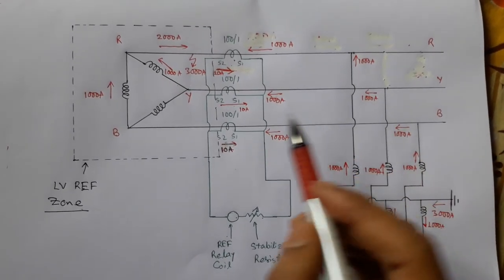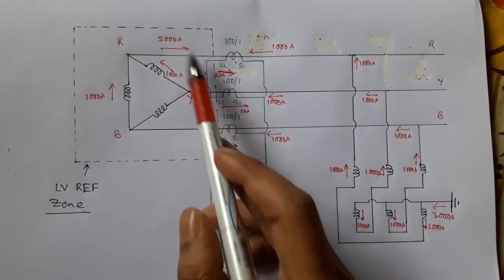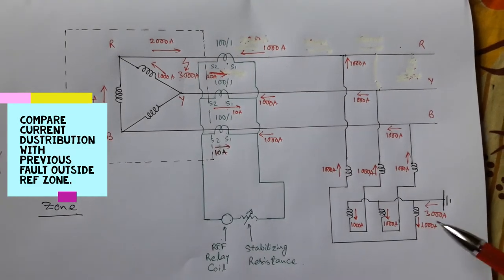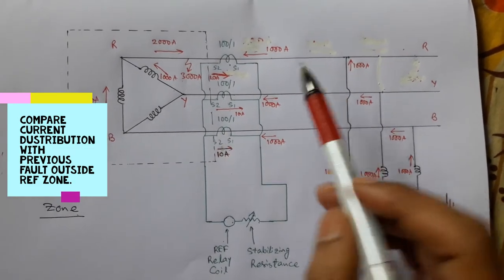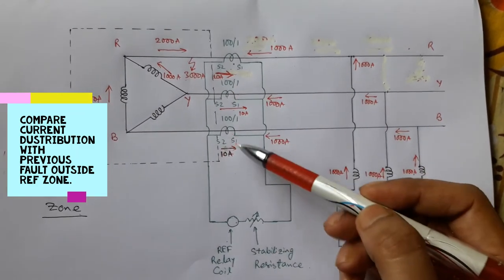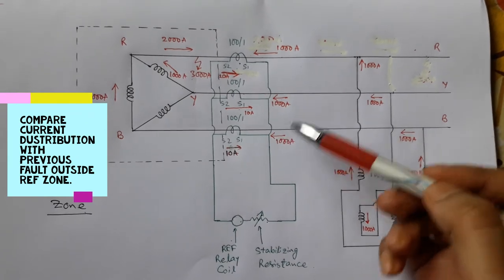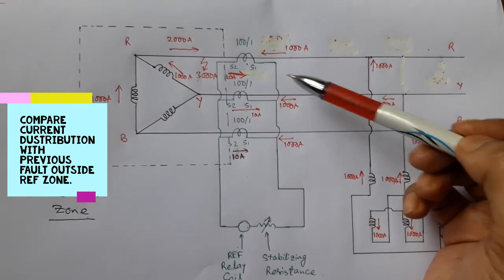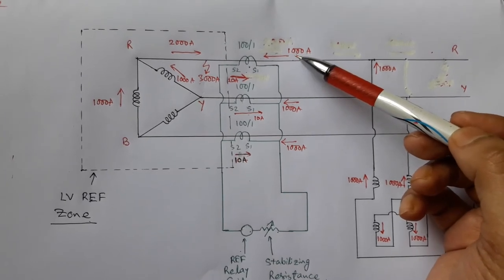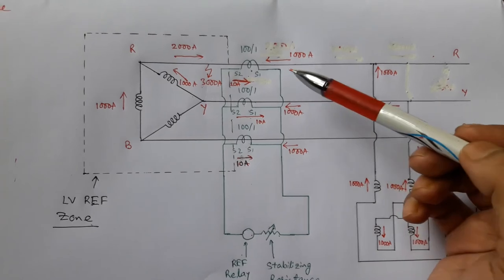But if the same fault of 3000 ampere occurs inside the protection zone, then this is how the primary current will flow. In that case, notice that the yellow and blue phase currents are the same and directions are also the same. But in the case of the red phase, the current is reduced from 2000 ampere to 1000 ampere, and the direction also reversed.